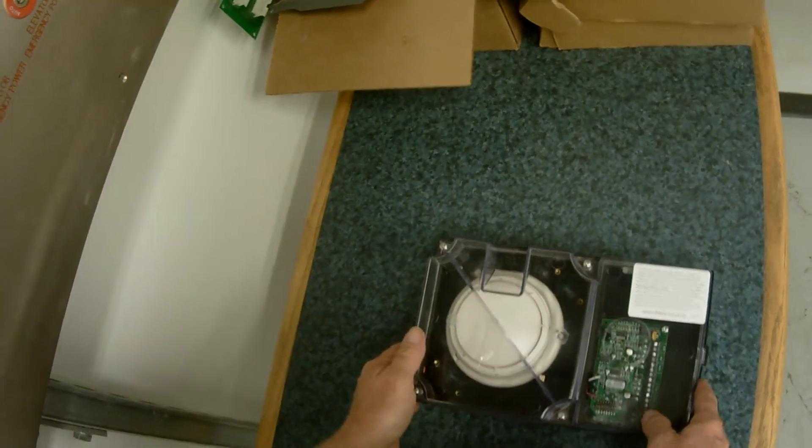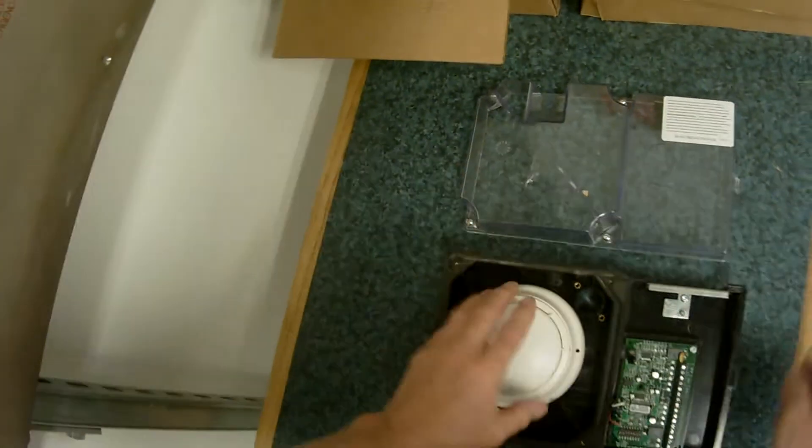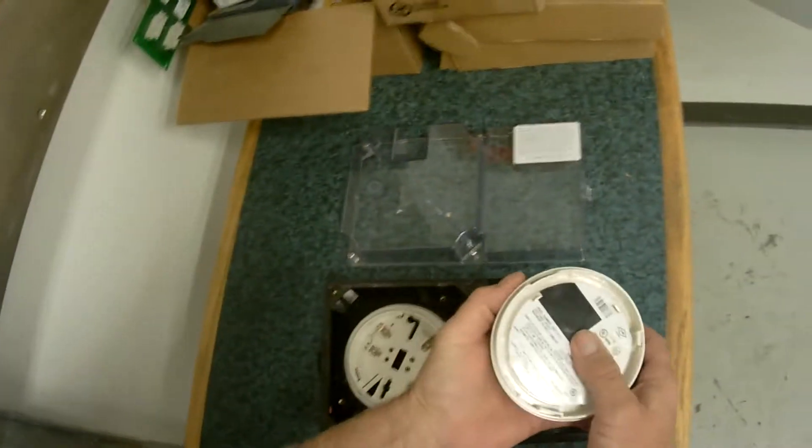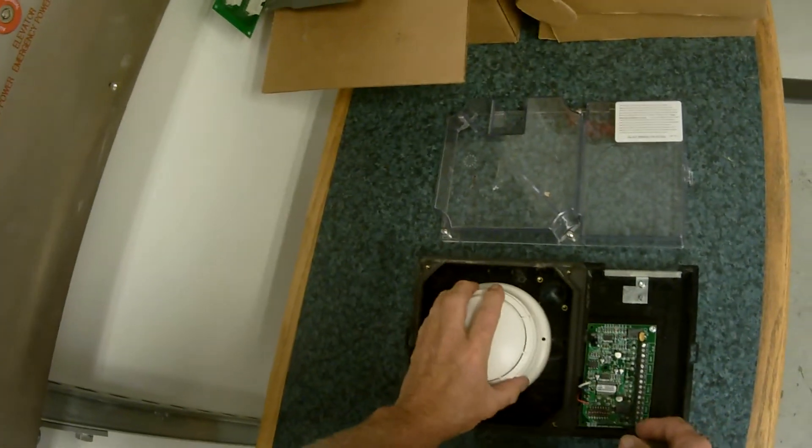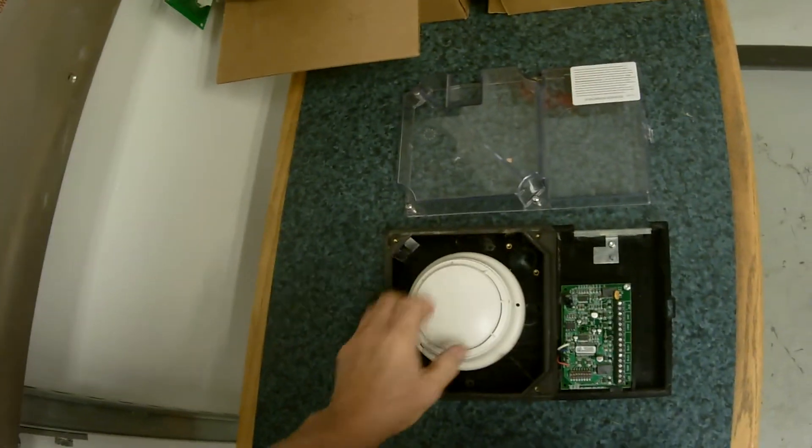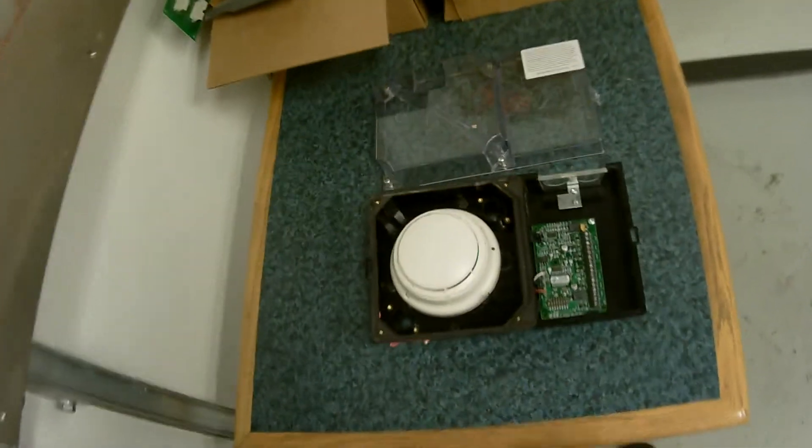Typically we get that dirty trouble, we take the head out, clean the head, put it back, we leave. We get called back the next day - same trouble again. We replace the head, leave, come back next day after that - same trouble again. We replace the board.